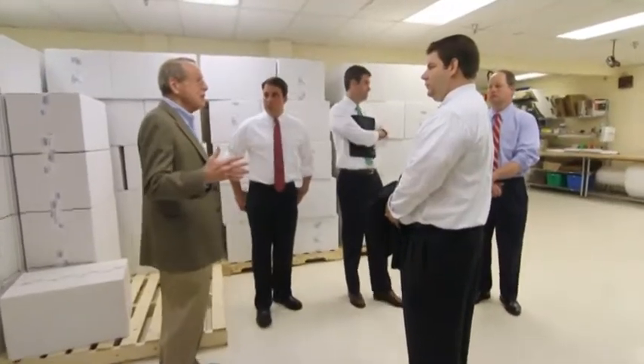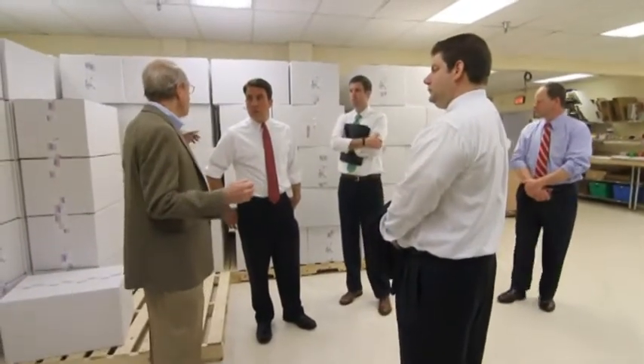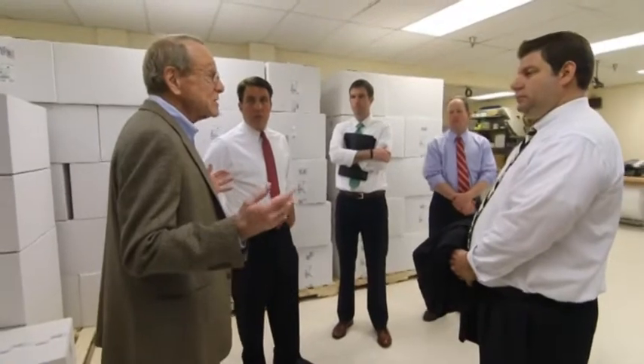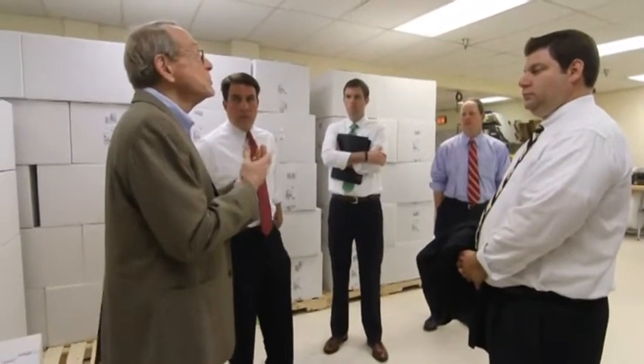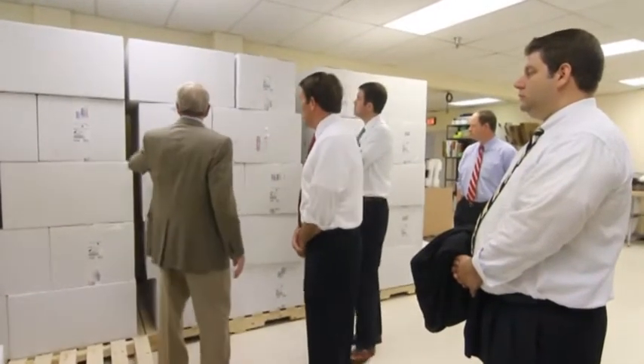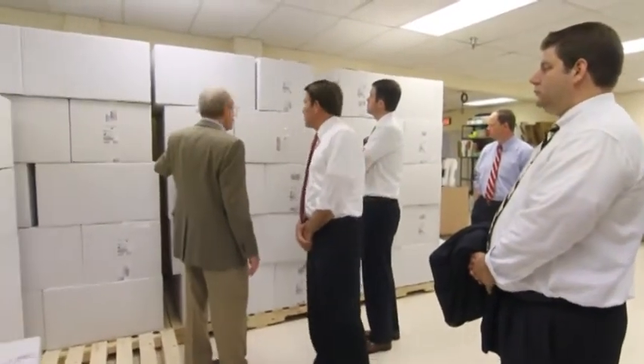You've got to have a substantial inventory, and at the same time our sets have been certified at three years. We accelerate the testing with heat, and we've also done real-time testing to make sure the pressure transducer that pushes against the tubing still works — that the tubing didn't get all hard and rigid in three years. We verify all of that. So all of these have three-year expiration dates — you can see it says 2017. These were built in April.